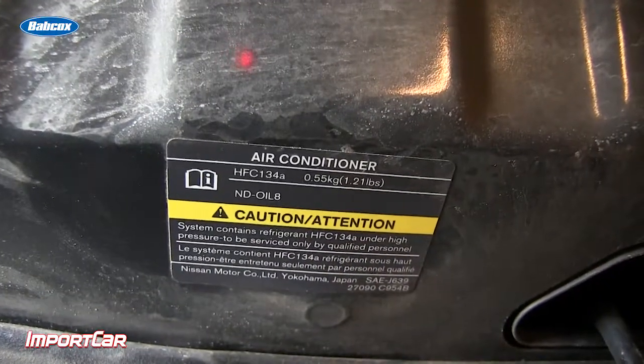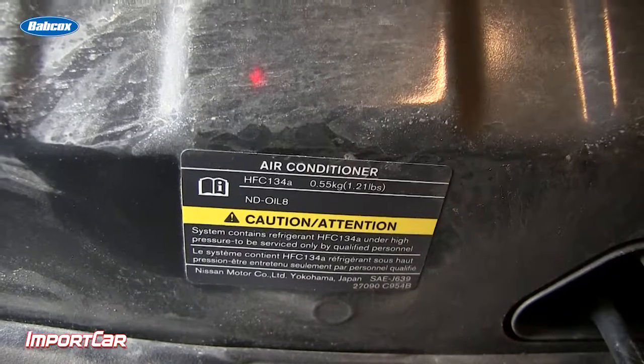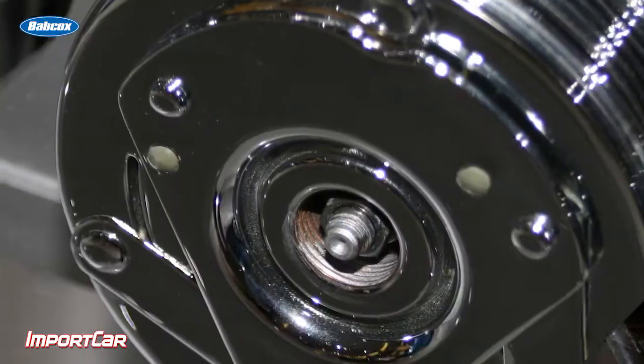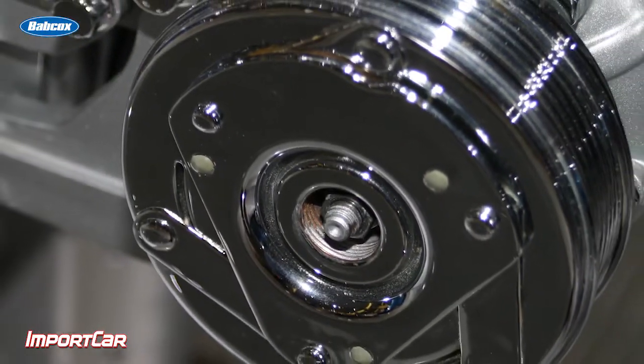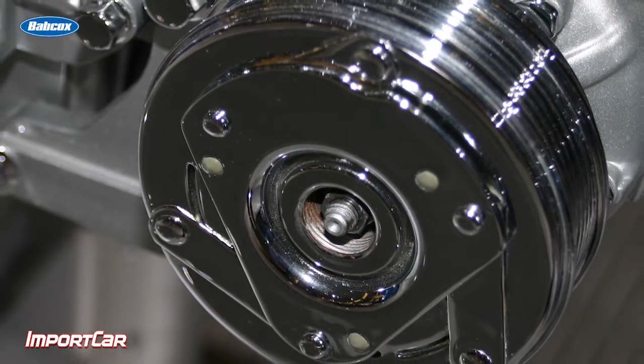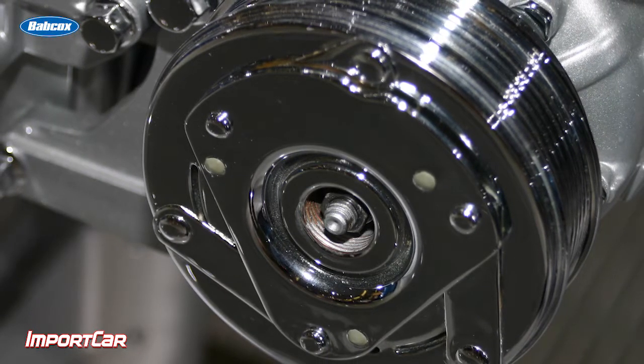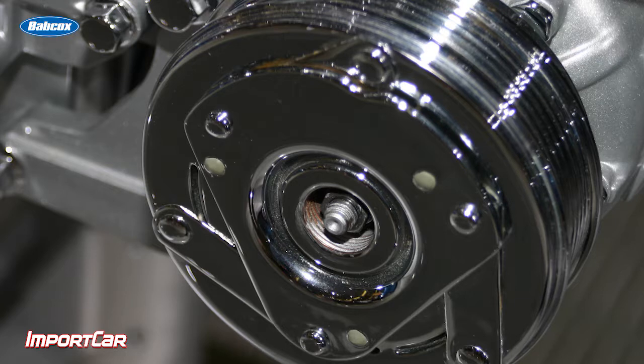After the system is fully checked for leaks, it is critical that the right amount is added. If you add too little or too much, the cooling properties of the HVAC system will not work properly, and you could possibly even damage a compressor or other components in the system. Refer to the service manual for the proper refrigerant and oil refill procedure.